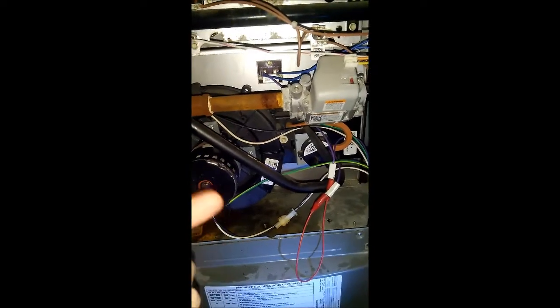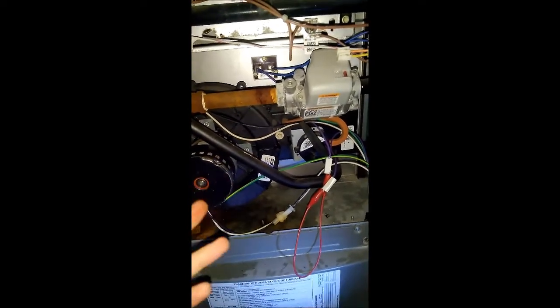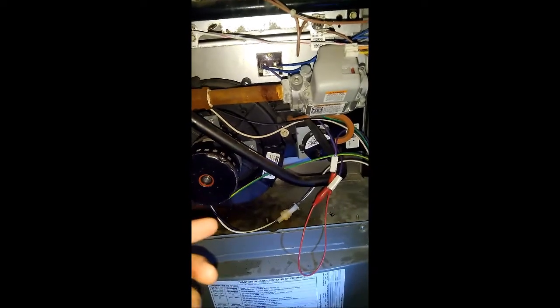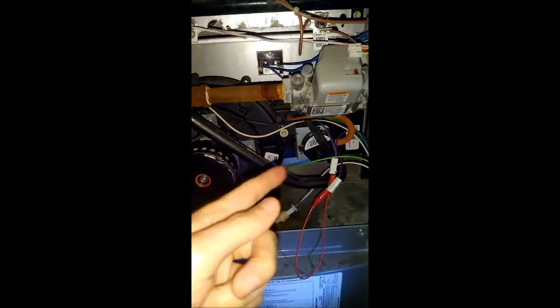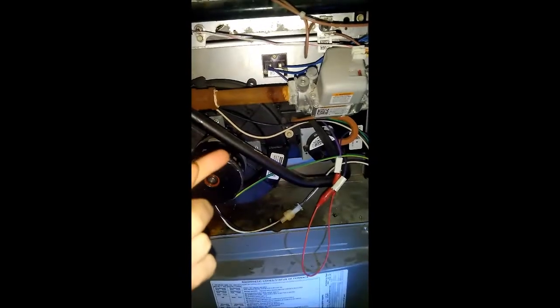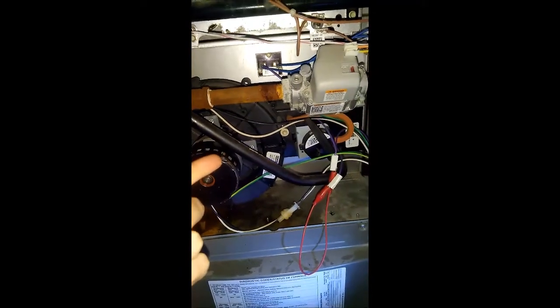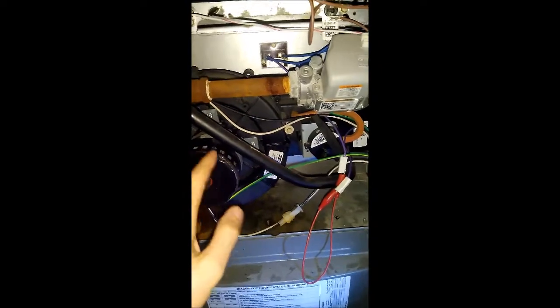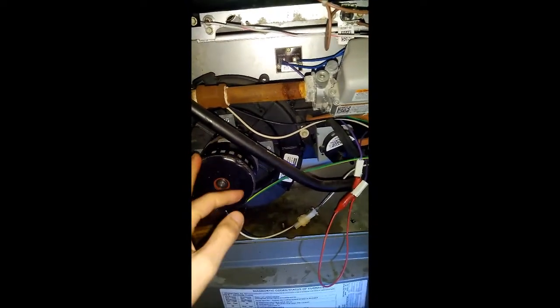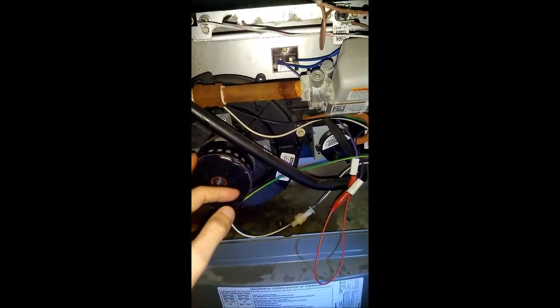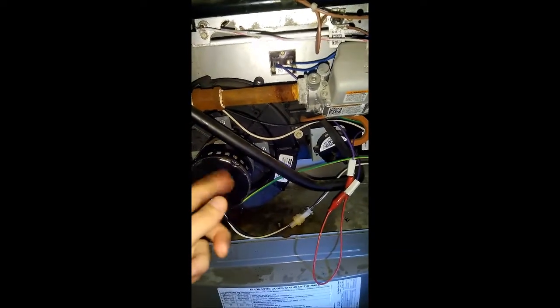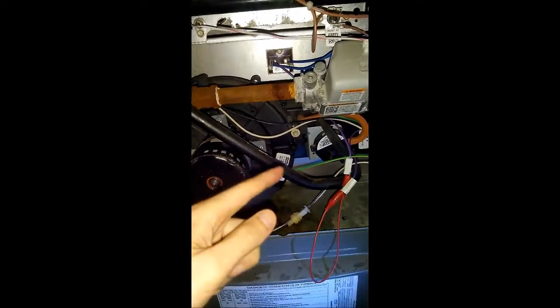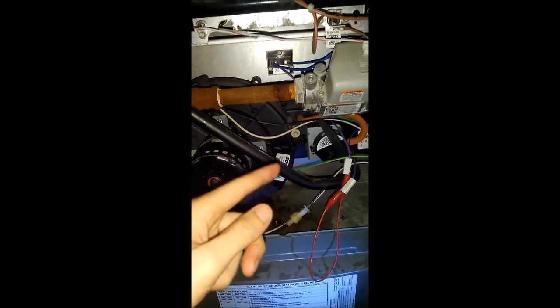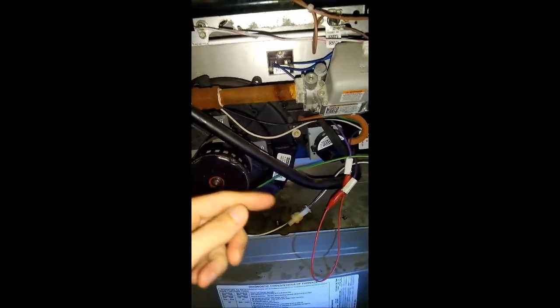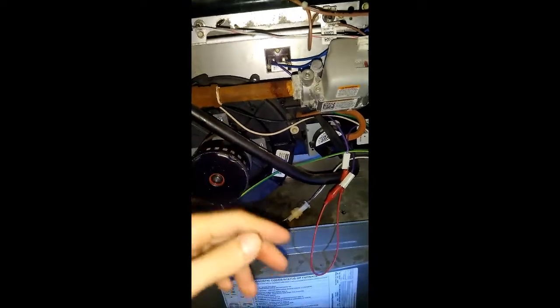And it'll start up your pilot and all that, and it'll burn the gas in your furnace. If it doesn't detect vacuum on that sensor, it won't allow the gas valve to open. It won't turn the furnace on. So basically, this thing has a certain amount of time, could be anywhere from several seconds to a couple of minutes, where the computer inside here is waiting to see vacuum on that valve. And if it sees sufficient vacuum, it'll allow it to turn on. If it doesn't see sufficient vacuum, it'll shut the whole system down and just abort.